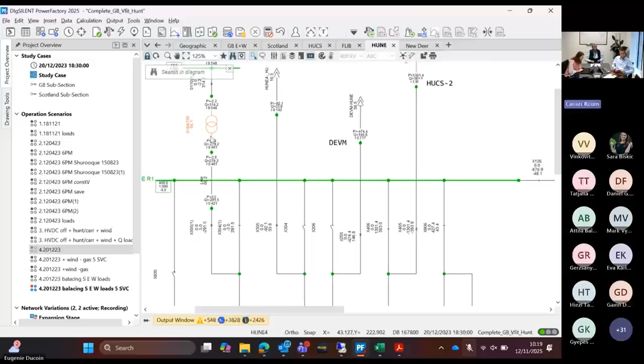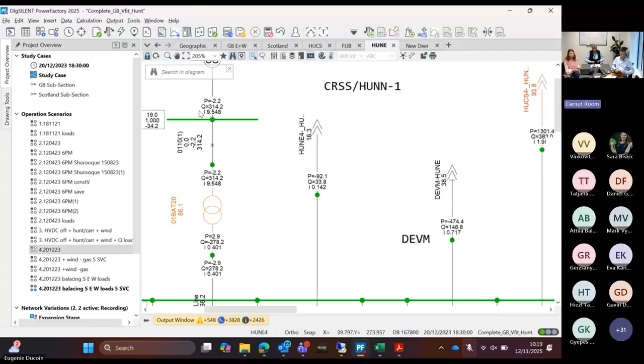So the final simulation I will do is to connect our stability island at Hunterstone. When I do that, the stability island can provide inertia, short circuit level, but also, more importantly in this case, reactive power. If I zoom in on our asset here, you can see Q is the reactive power, providing 314 megavars, which means the voltages are back to the levels they should be.